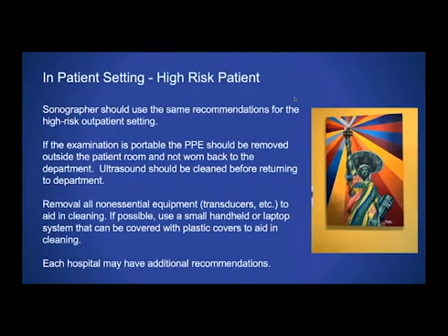For ICU patients, I think Arun went over a lot of the things you need to do. Again, we need to pay a little bit higher attention to cleaning the entire machine, the transducer, and the cord of the transducer. Again, ideally, if you have one of these small handheld or laptop systems that can be completely covered with plastic, that is going to aid in cleaning. You still need to use your low-level disinfectant, even if you use the plastic cover. Remember that the virus does live longer on plastic, so you need to be very careful disposing of those plastic covers. And again, you should follow the recommendations for PPE in your center.